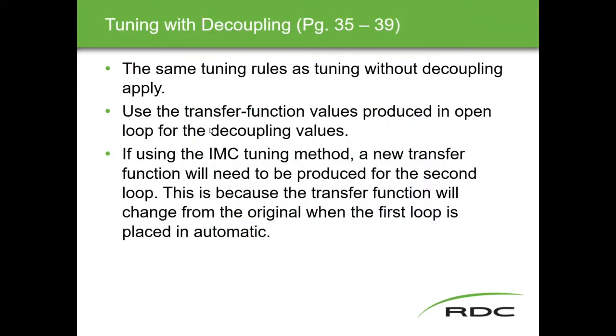Tuning with decoupling basically follows the same tuning rules as without decoupling, except you're using the transfer function values produced in open loop to calculate the decoupling values. One note: if using the IMC tuning method — which we haven't covered yet — a new step test needs to be produced for the second loop. These are specific characteristics for tuning multi-variable loops.